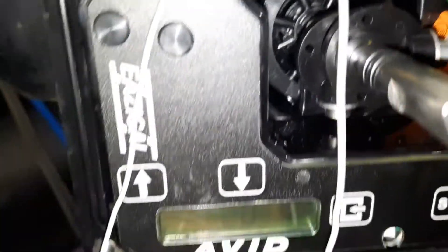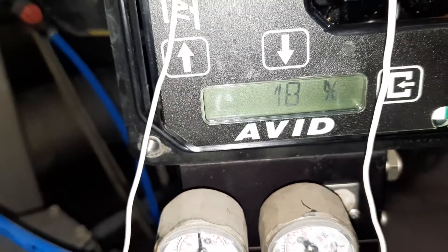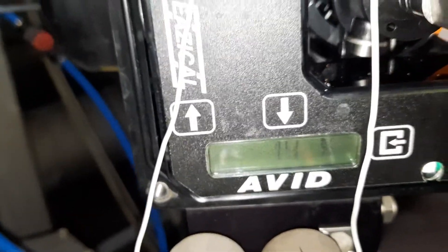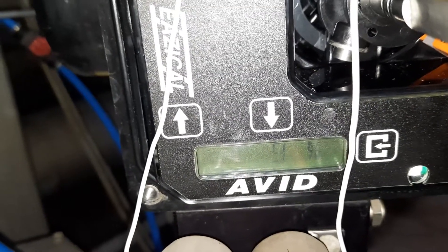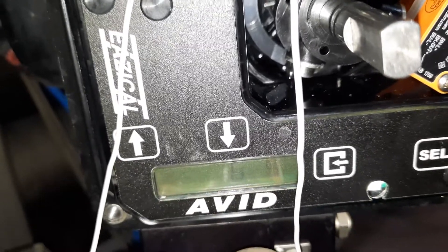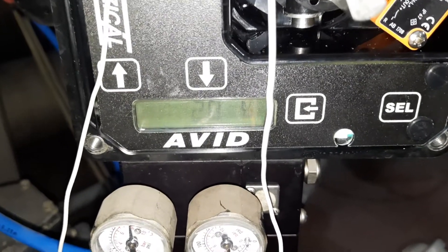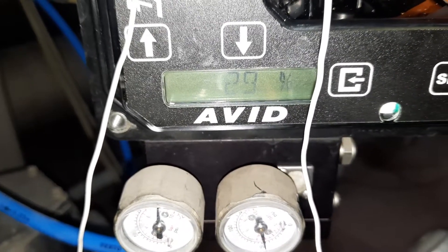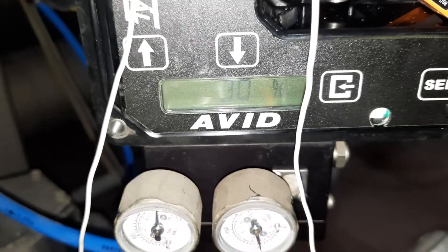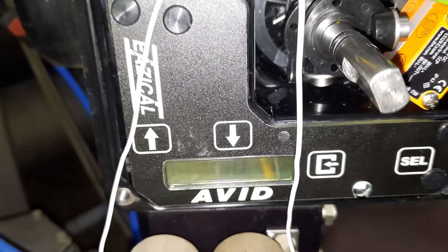I will put it to 8 milliamps — it's going down again. At 8 milliamps it should be about 25% only. It's going down — 29, 29... about 30%. It seems good, no problem for this one.